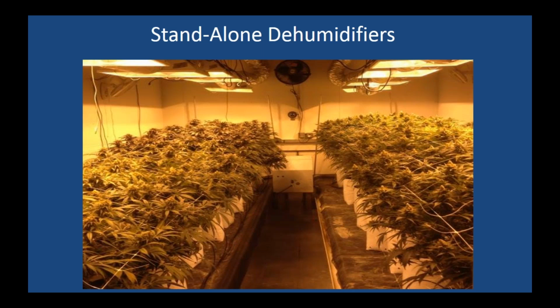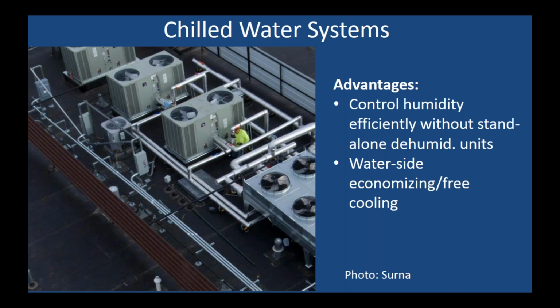For medium-sized or larger grows, there are a couple options to address that added cooling load. The first is chilled water systems, like the one shown here. The other option is rooftop air conditioning units with hot gas reheat, using heat recovery from the condenser rather than electric resistance. Another advantage of chilled water is the ability to do free cooling in cooler months, using cool outdoor air to cool the water rather than the chiller system, which is very efficient.